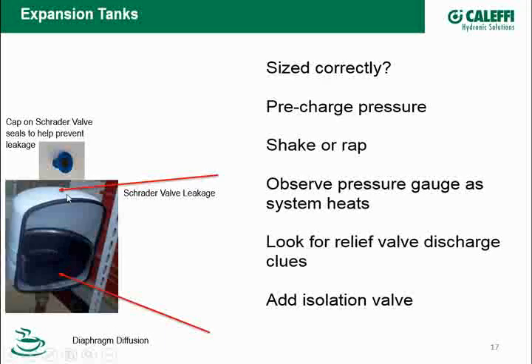Now, what can happen on these is this is just a Schrader valve, just like a tire stem that you have on your car, and they do leak, just like you can lose air out of your tires on your car, your truck, or your lawnmower, whatever it might be. So this cap that comes with them really needs to be on there to give you a second seal on that Schrader valve. So if this is gone when you get to the job, then keep some of these with you, or just take one off the tires on your truck and put it on there, because they can lose pressure over the years through this little Schrader valve.